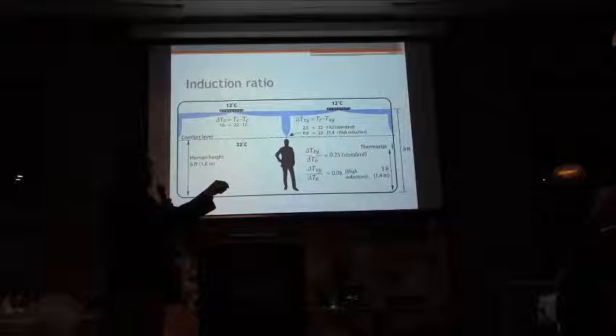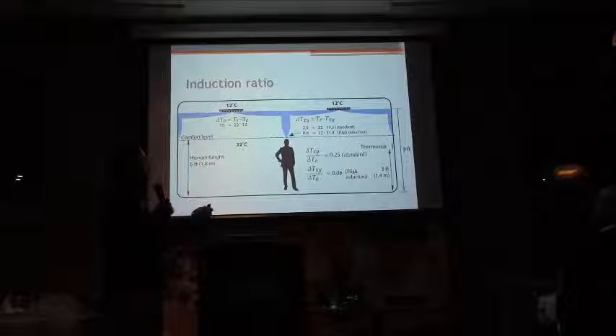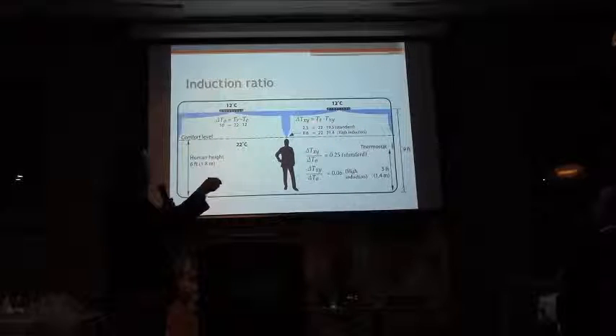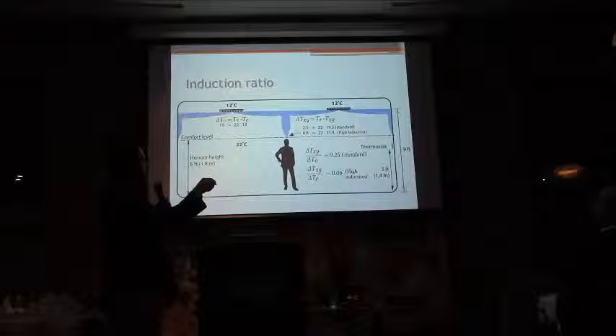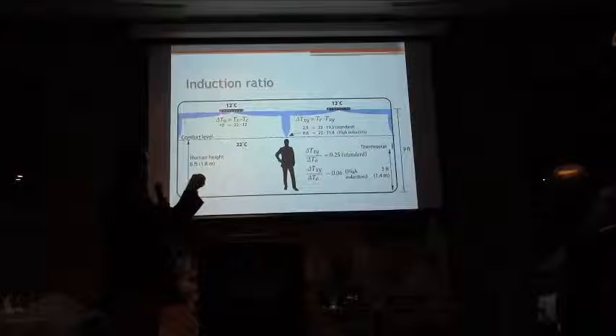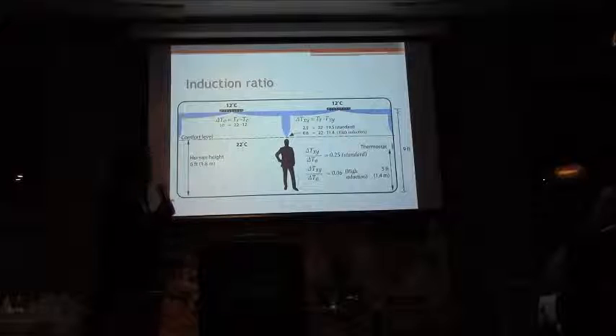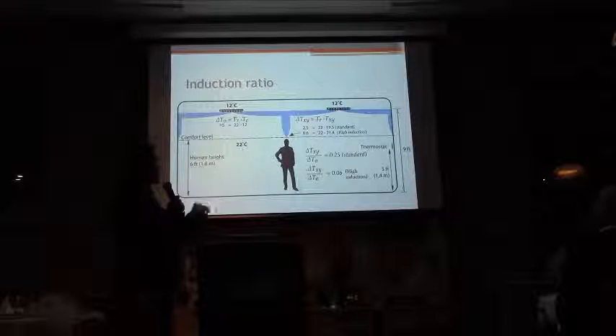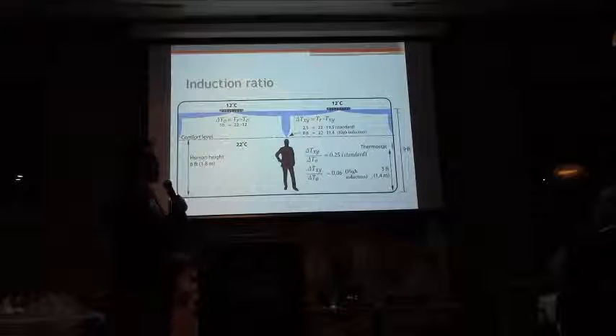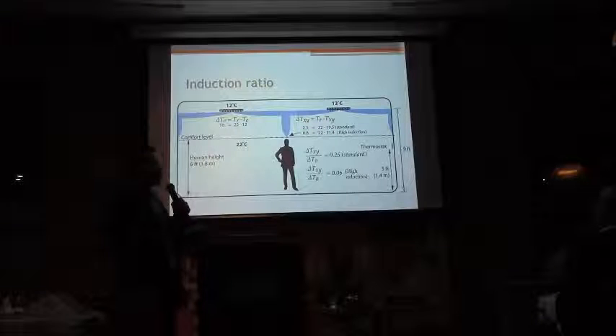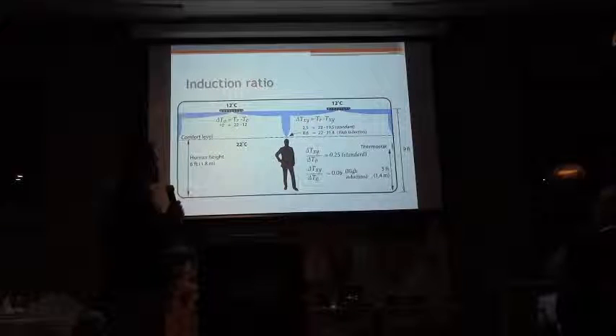So there is delta TXY and delta TO. Delta TXY is T room minus TXY. TXY is the temperature of the air once it reaches the occupied zone here. And delta TO is T room minus TO, which is the supply air temperature. Everything's in Celsius in there, because induction is a European technology, so they work in Celsius over there.